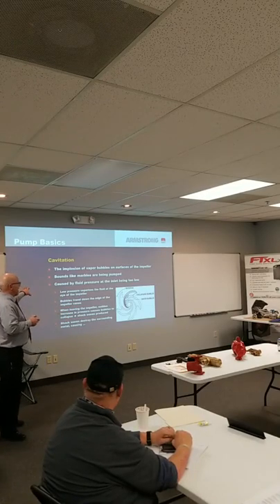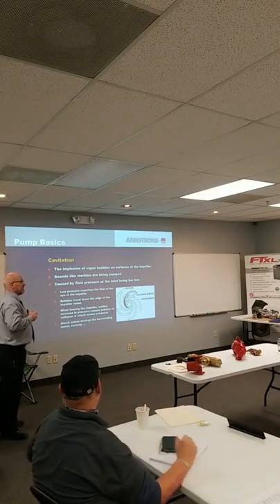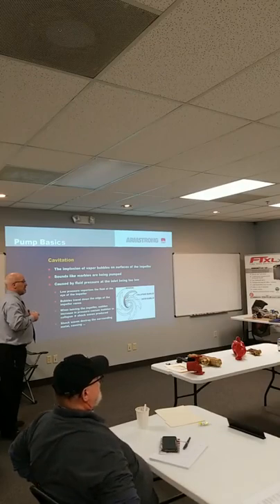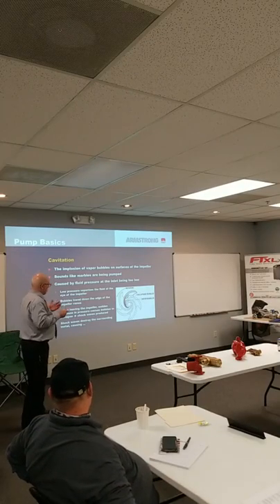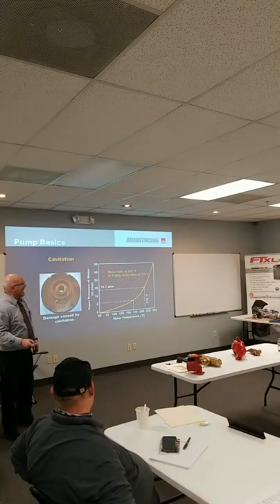We're starving that pump so it pulls a vacuum. That's what cavitation is. If you go below atmospheric pressure, that's also a source of air. If you got a mechanical seal, well, if you're leaking in through the seal, yeah. But cavitation can be nasty.